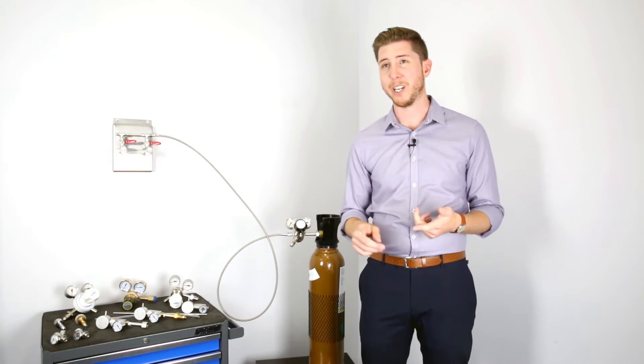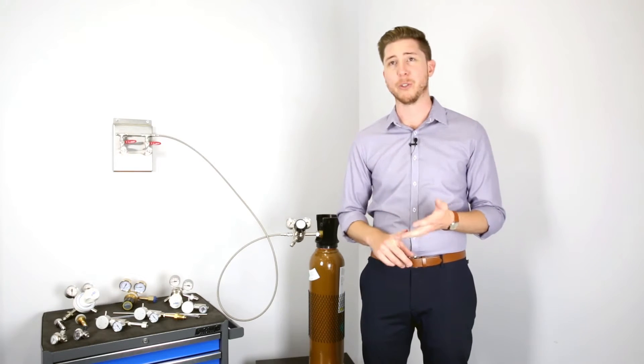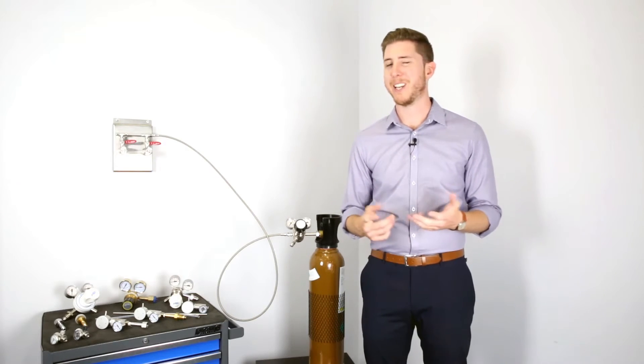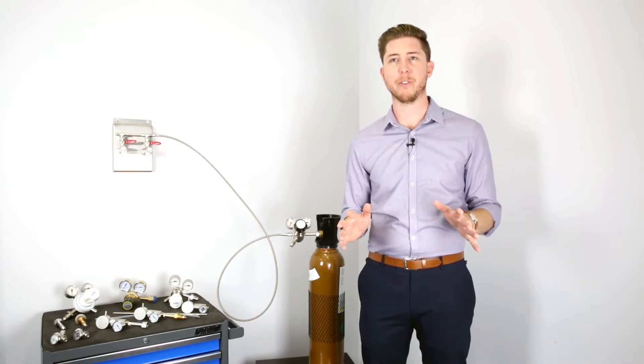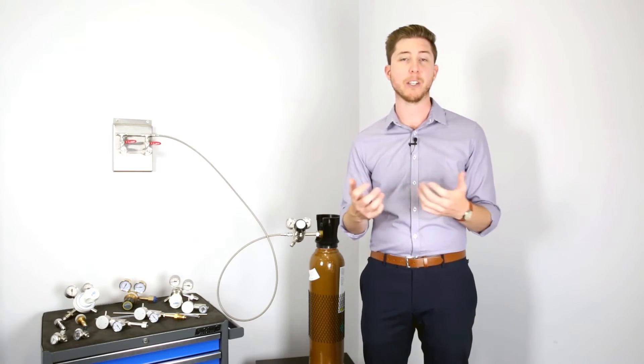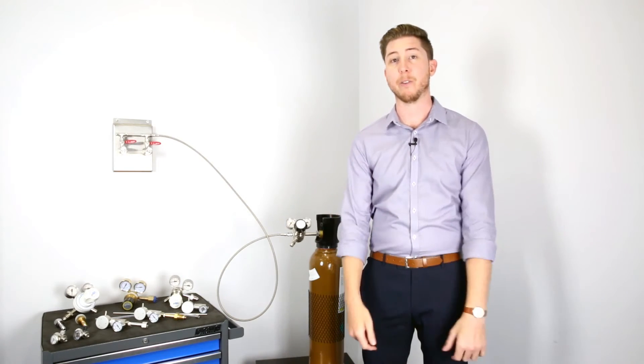Corrosive gases including chlorine, ammonia, NO, and NO2 require the use of stainless steel materials and Teflon tubing. Standard Tygon tubing is not satisfactory for these gases as the gas will actually adsorb on the inside of the tubing and you'll get little to no gas concentration at the end of your line.